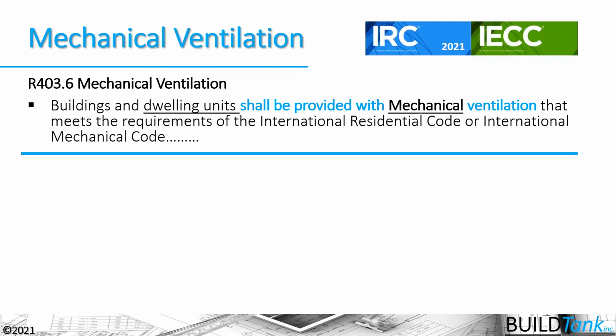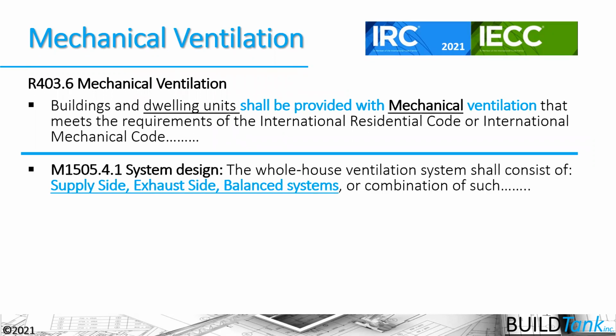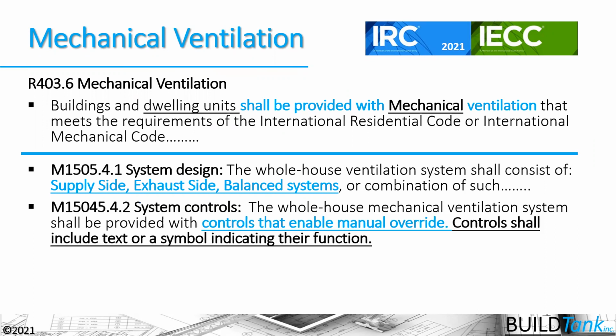Whole house controlled mechanical ventilation shall be provided. This mechanical ventilation, again, down to the dwelling unit level in multifamily homes, is needed. And it's called out in the IRC and the IECC now both. We're allowed to use supply side, exhaust side, or balanced ventilation systems according to the code. But we have to have some type of control that enables manual override. So, for example, if I have a red pollution day outside, I might not want to ventilate. Or if I have fire smoke hanging around like we had in Denver over this past summer, we might not want to bring air from the outside to the inside. So I have to be able to override those controls.